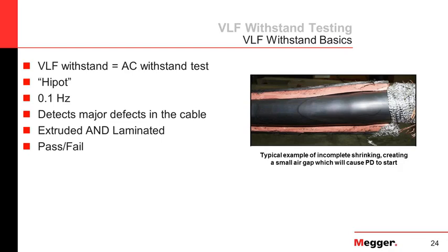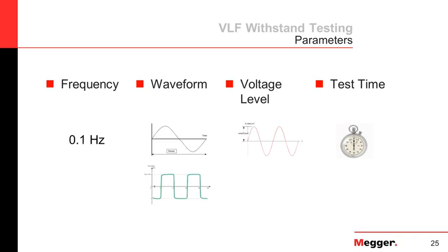There's an example on the right-hand side showing a bubble in the heat shrink where someone didn't shrink it all the way, causing partial discharge or little discharges to occur, which caused a breakdown. Something as simple as incomplete shrinking can cause a breakdown — and this is what a VLF test could detect. To run the test you need to know four parameters: frequency, waveform, voltage level, and test time. Frequency is easy — use 0.1 hertz. For waveform you have two options: sinusoidal and cosine rectangular.